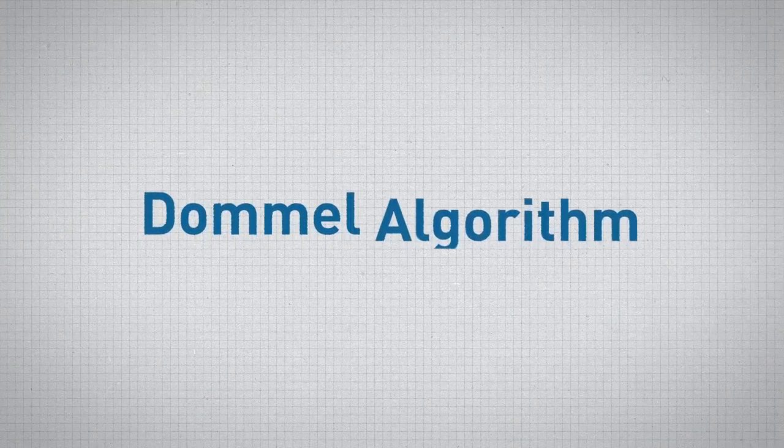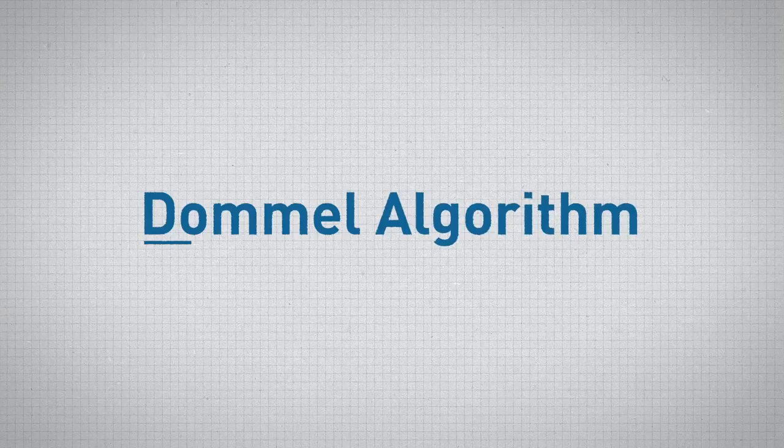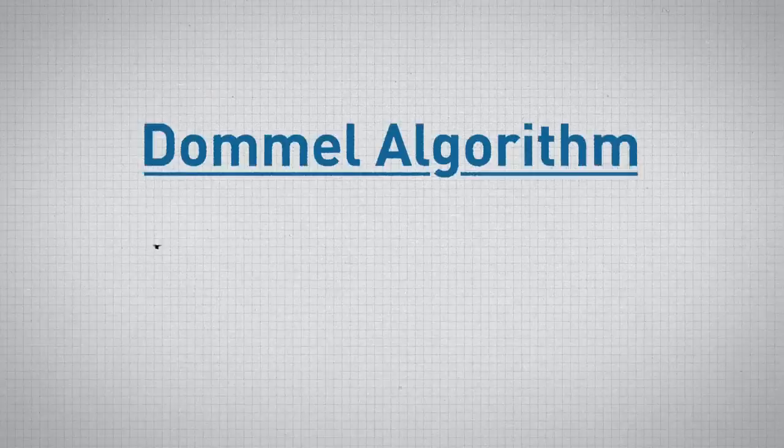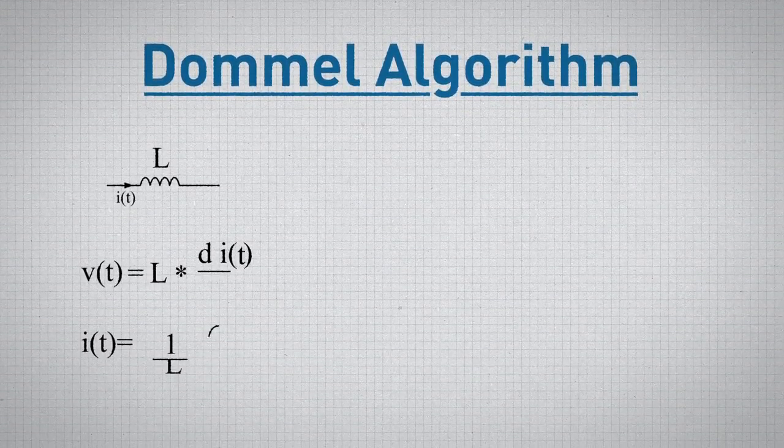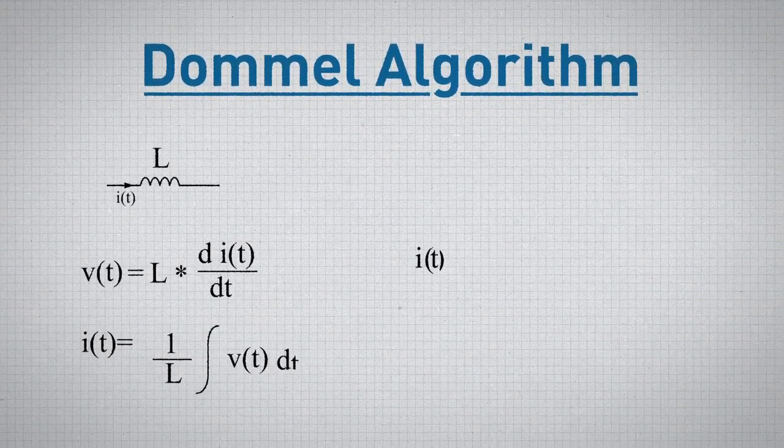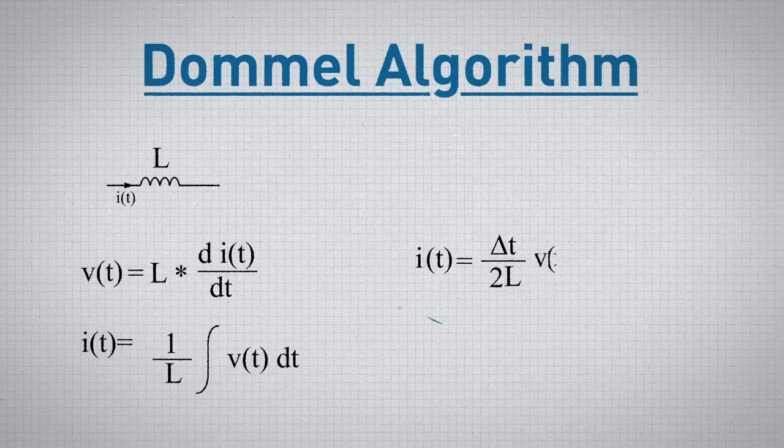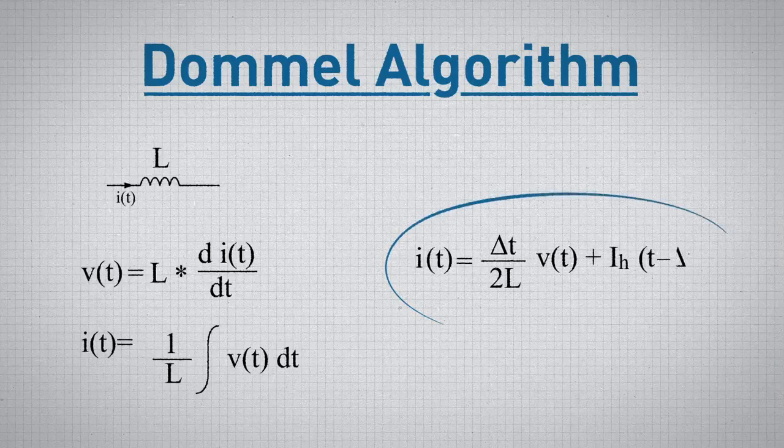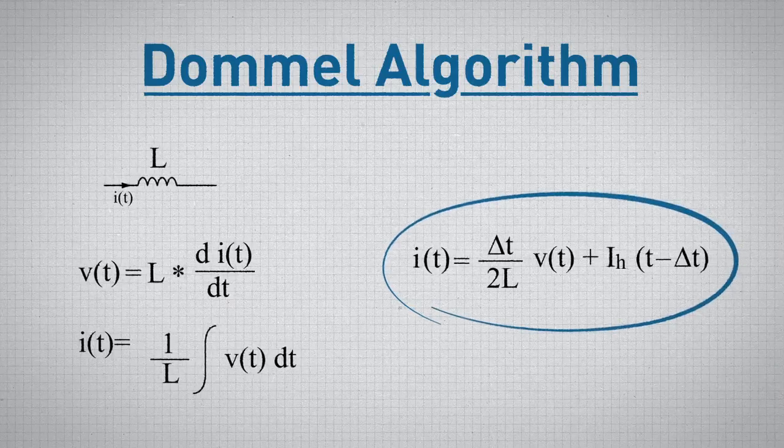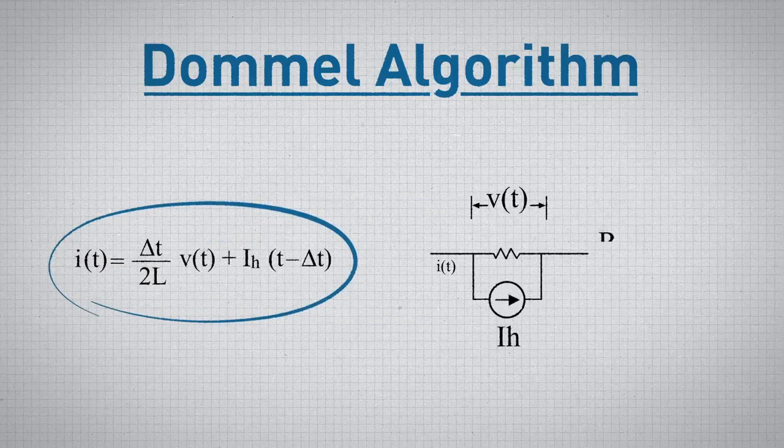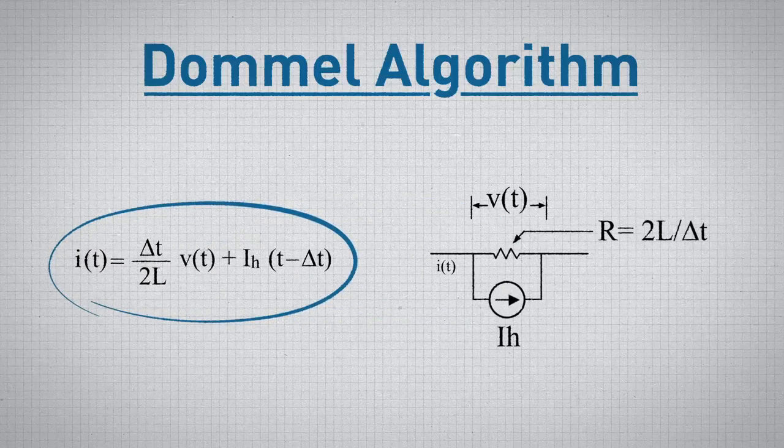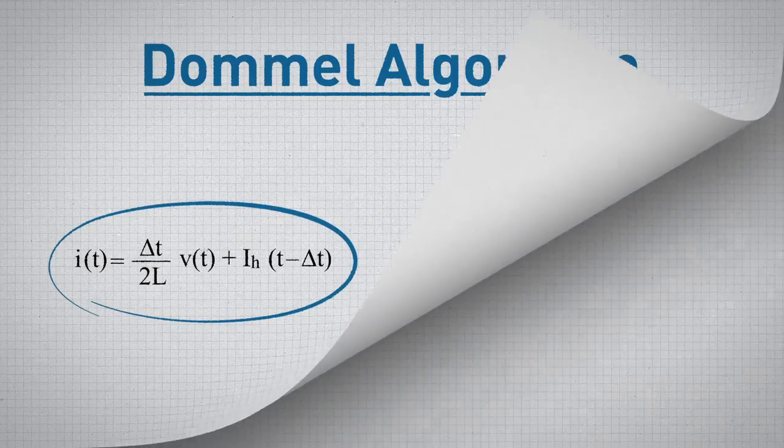The RTDS simulator runs electromagnetic transient simulations based on the Dommel algorithm. The Dommel algorithm converts differential equations to linear algebraic equations using the trapezoidal rule of integration. This allows all elements within a given network to be represented by an equivalent current source and conductance.